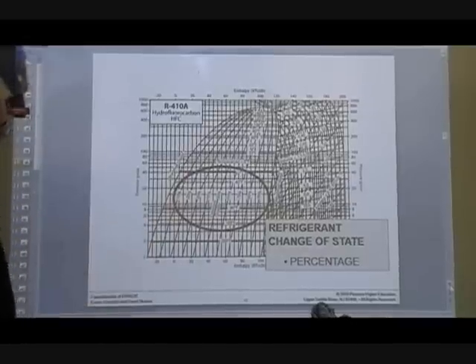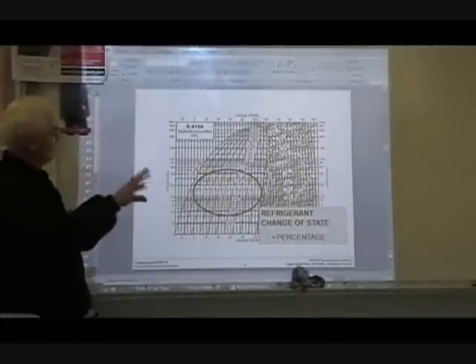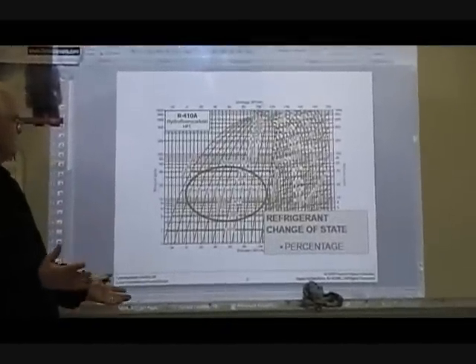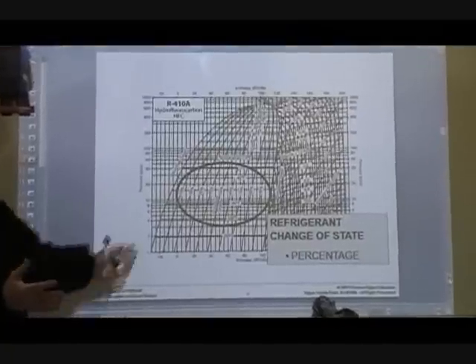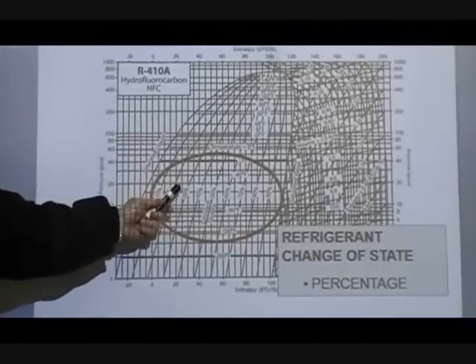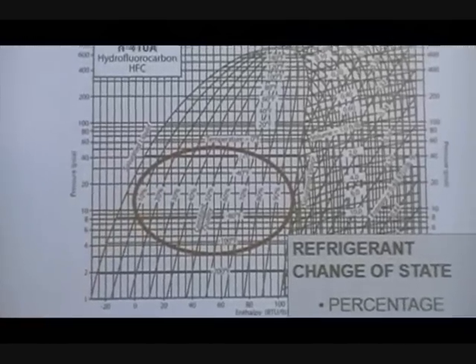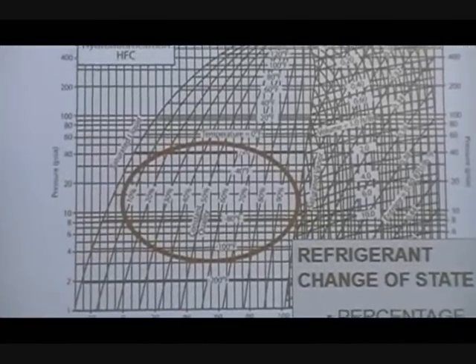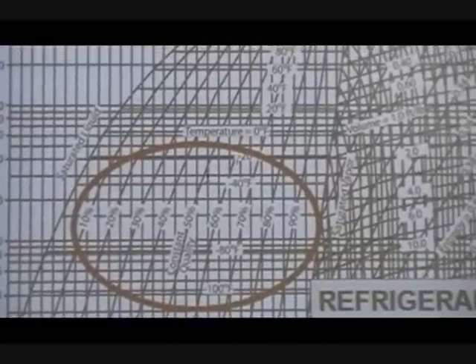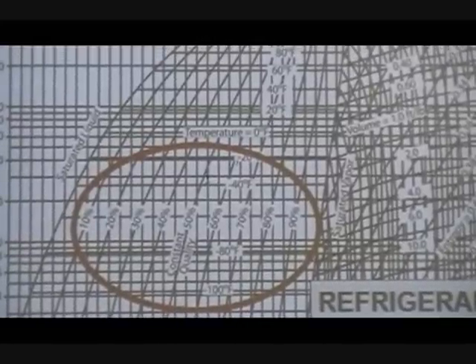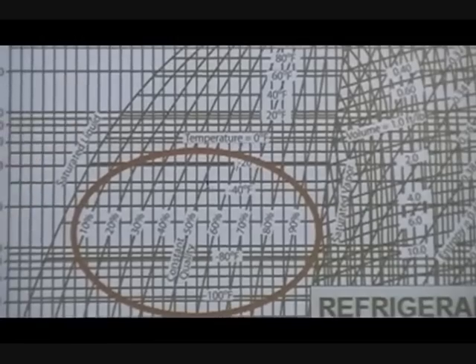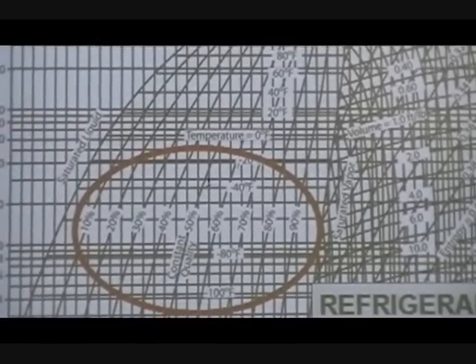Let's say you never achieve 100 percent liquid. Say when that refrigerant is going through your liquid line entering the metering device, you've got 80 percent liquid and 20 percent vapor — it never gets beyond this line here. What does that tell you? You've got condenser problems, or your system is not charged properly. That tells you how important having 100 percent liquid is in that system.